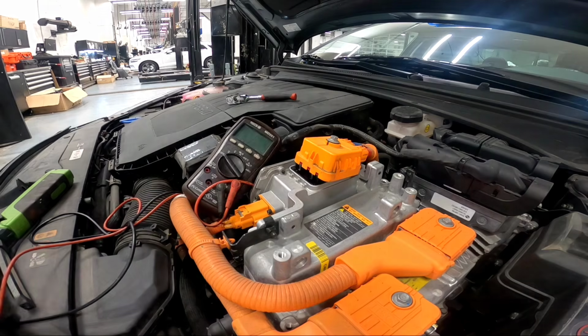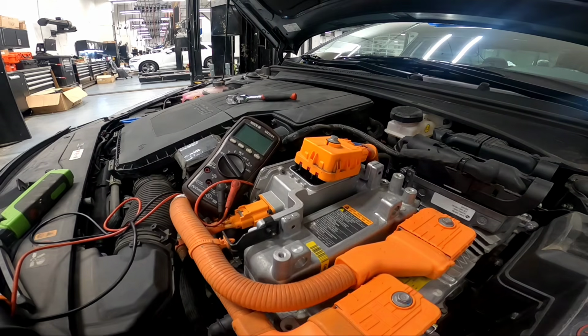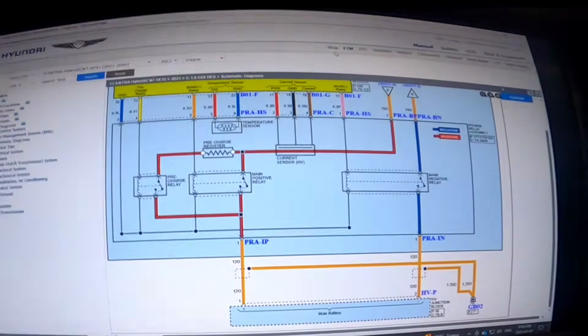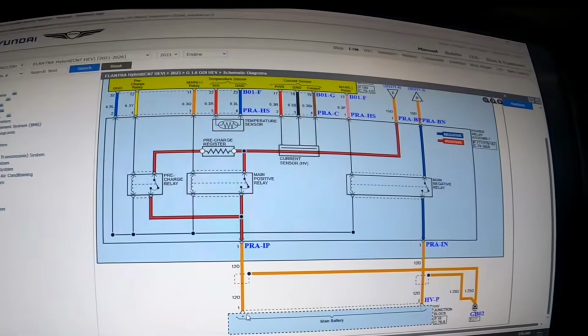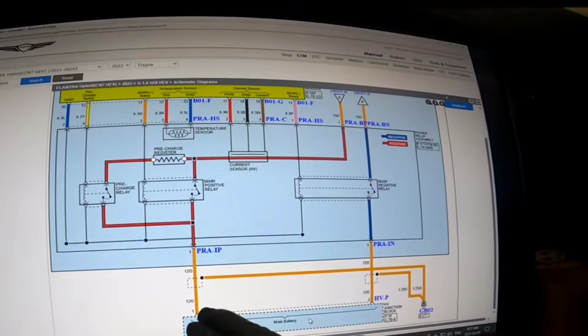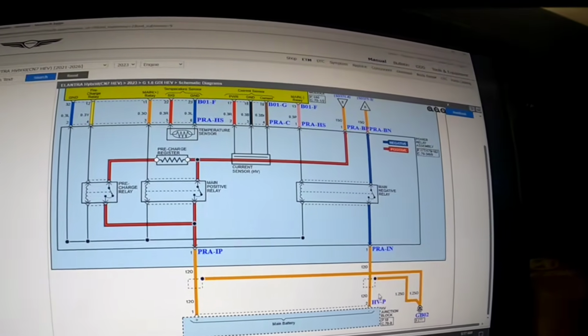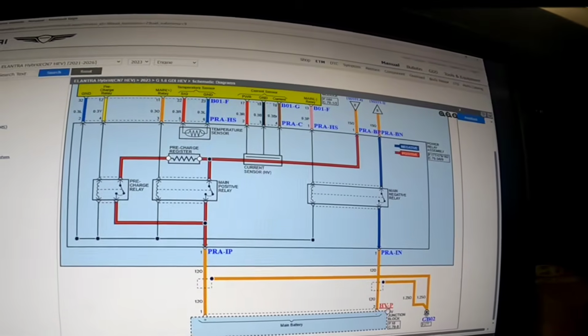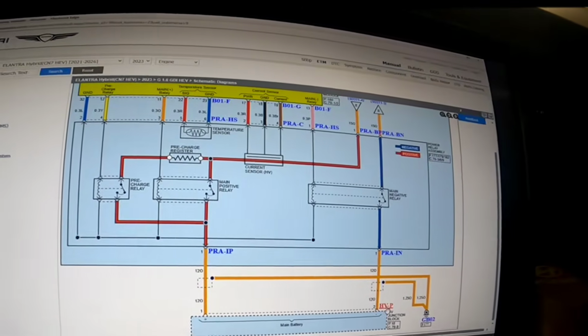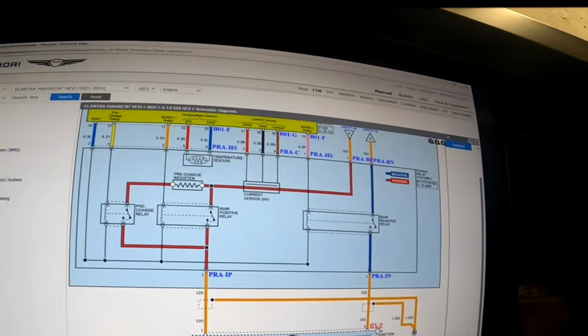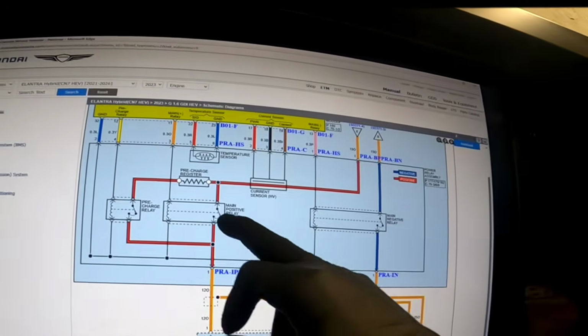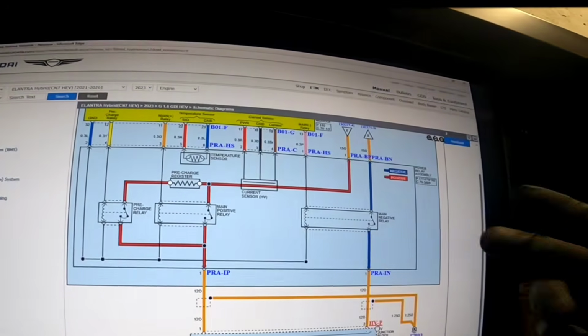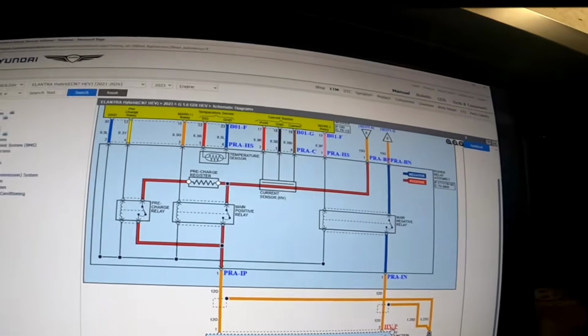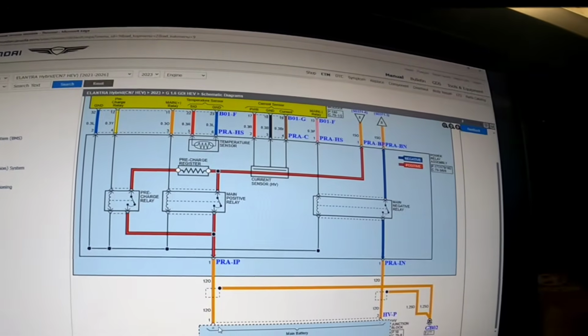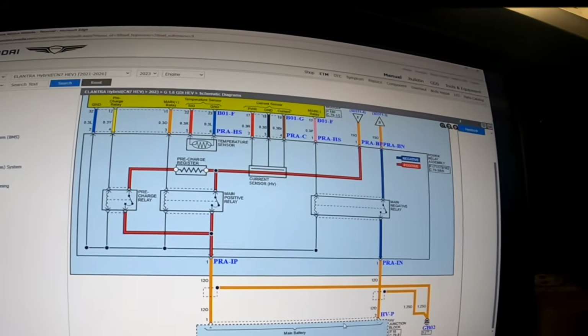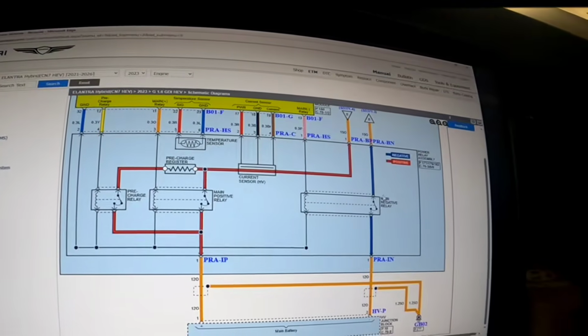Let's turn this off. Let's just go straight to our wiring diagram first. So now the shut-off process, what we're doing is we unplug this here, right, and remove this H connection here, HVP, and we measure if we have voltage still. By doing that, we make sure our main relays are not on, right? But what happened right now is we got 225 volts there, so meaning our relay is on here.